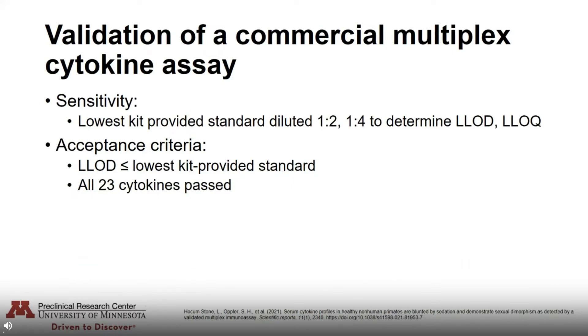Finally, we looked at sensitivity — the ability of the kit to detect low-range concentrations of analytes. We took the lowest kit-provided standard and diluted it at 1:2 and 1:4 to determine the lower limit of detection and the lower limit of quantitation. Our acceptance criteria was that the lower limit of detection was less than or equal to the lowest kit-provided standard concentration, and with this criteria all 23 cytokines passed.